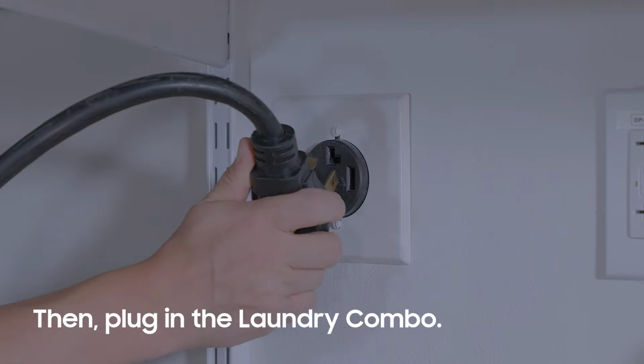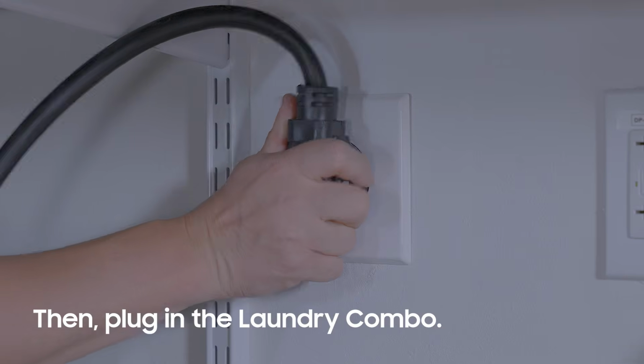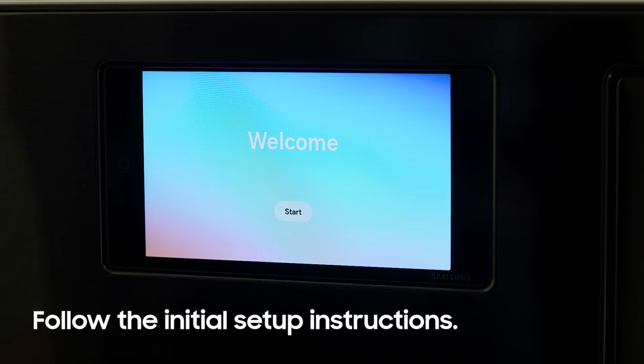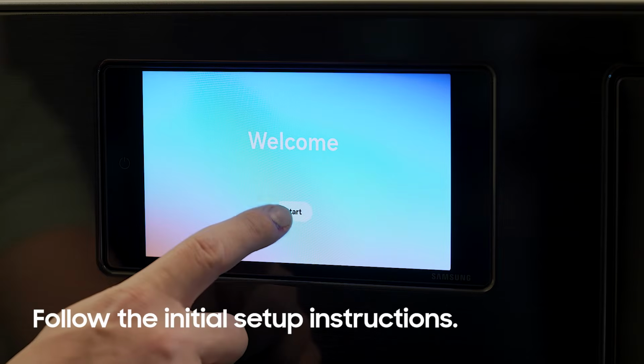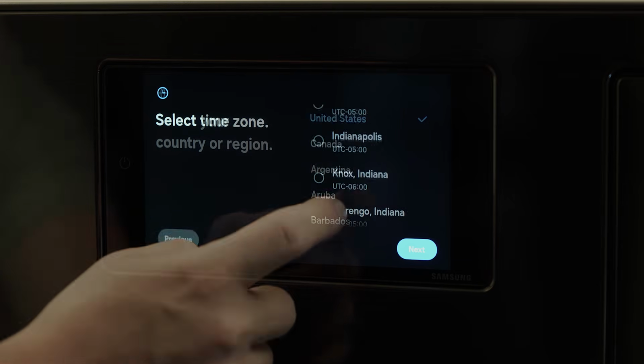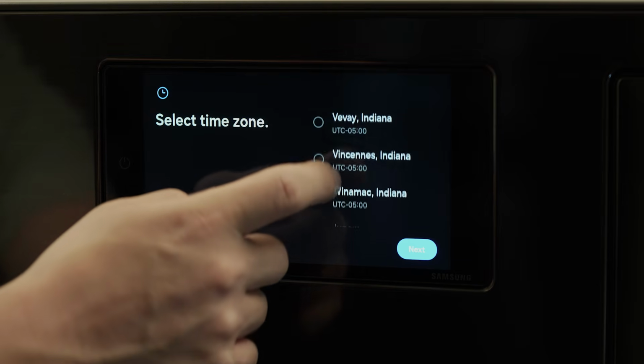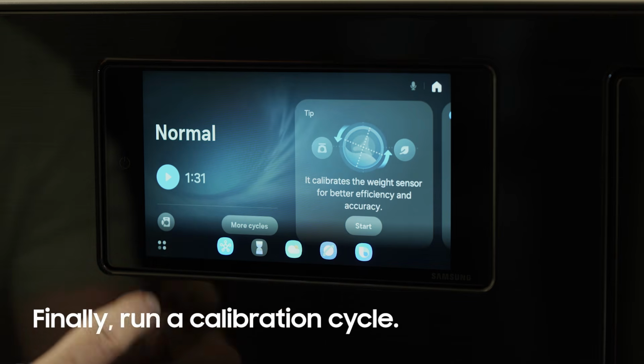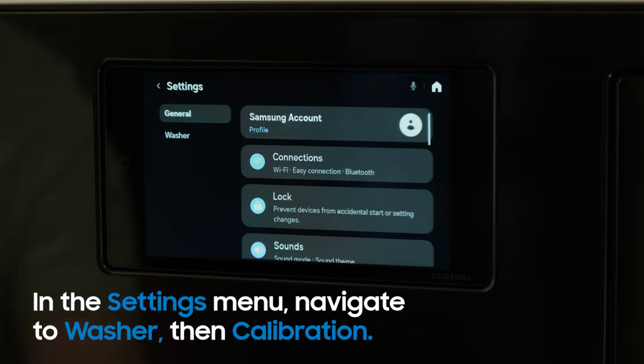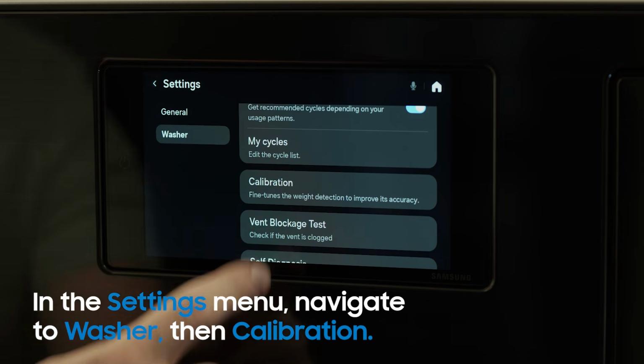Now you can plug in the unit and turn it on. The main screen will allow you to select certain initial settings such as language and run you through a tutorial. It is recommended at this time to run a calibration cycle. Select Settings, Washer, Calibration, and start the sequence.